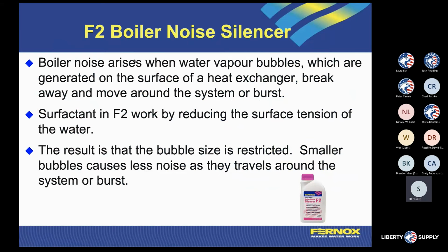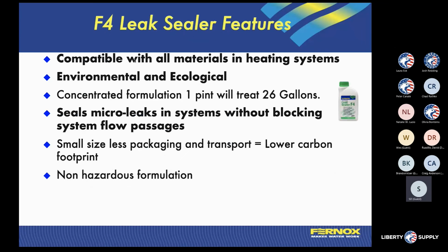The next product that we talk about a little bit is our noise silencer. This is for reducing the oxygenation around different contaminants in the system. A lot of times you hear popping and hissing in an old cast iron or steel-based boiler or tube boiler. This will help isolate some of those noises to try to get the system a little bit quieter, maybe to get to a place where you can service it out of season, or maybe you're going to change that boiler out in the next season. So this is a tool that you have to deal with that.